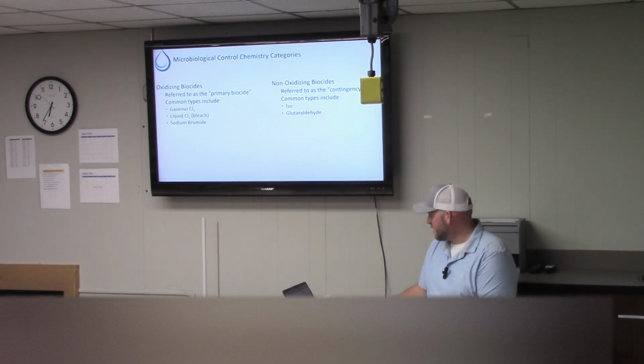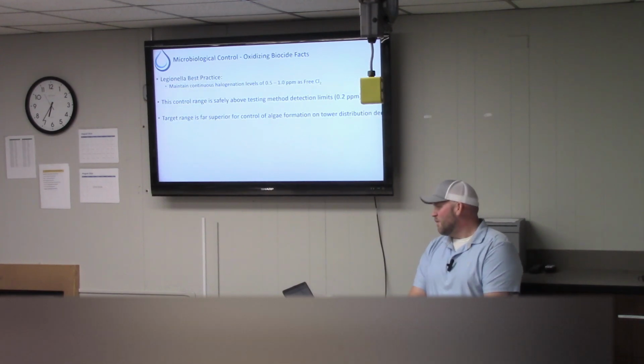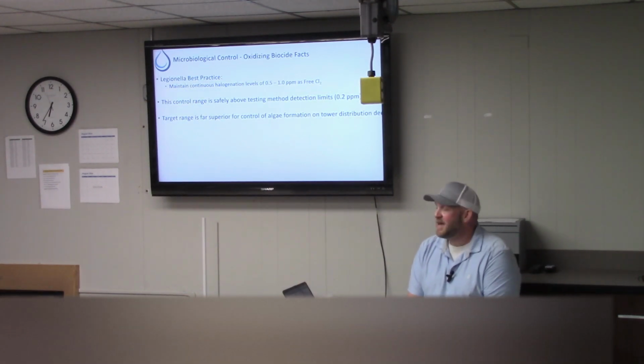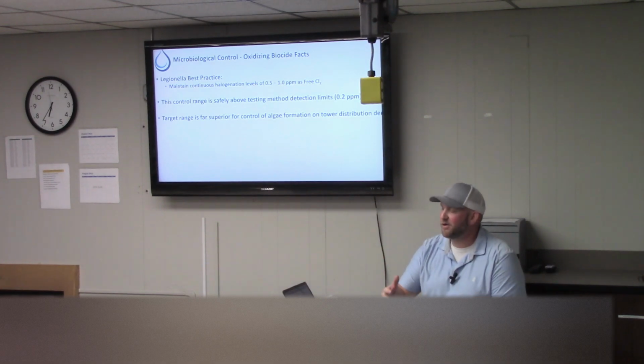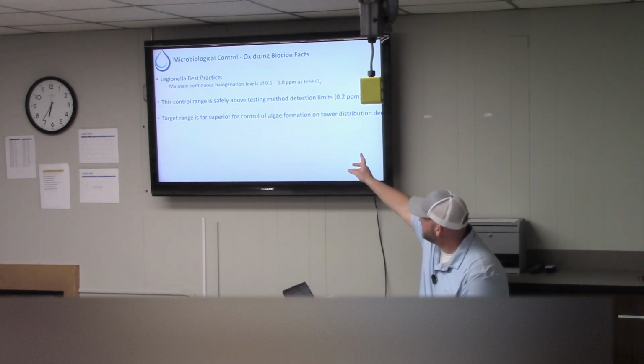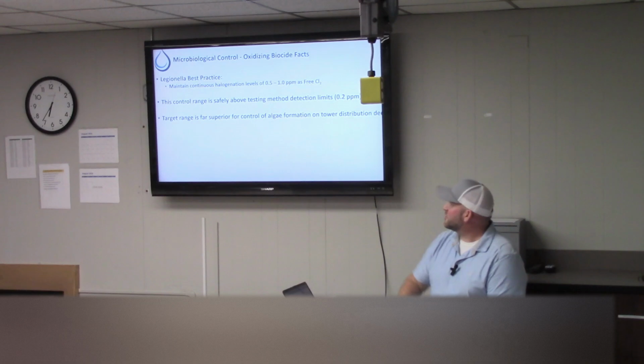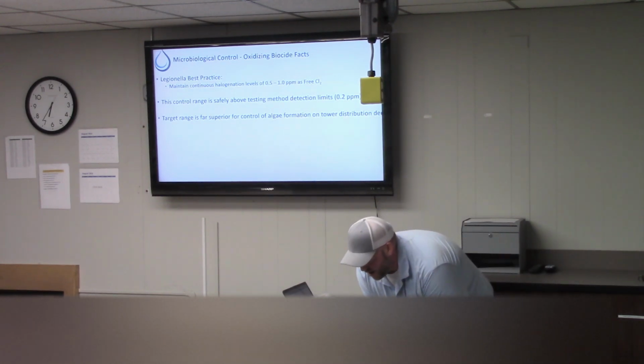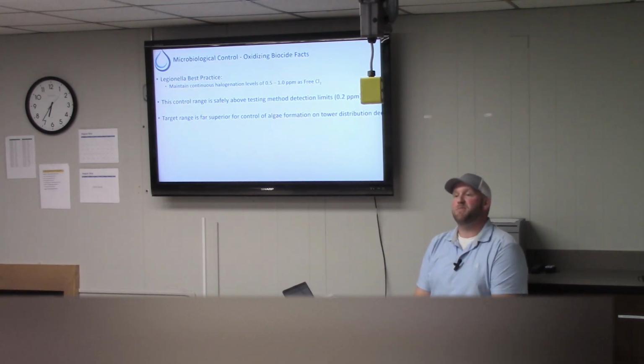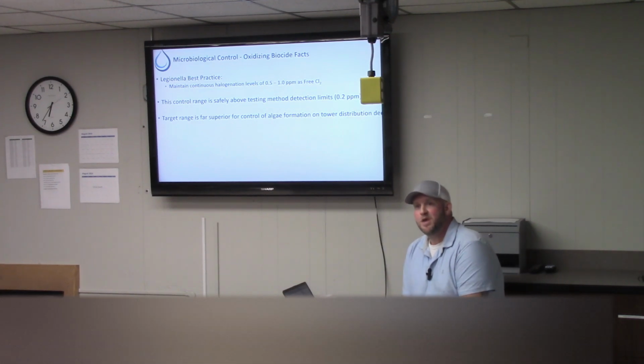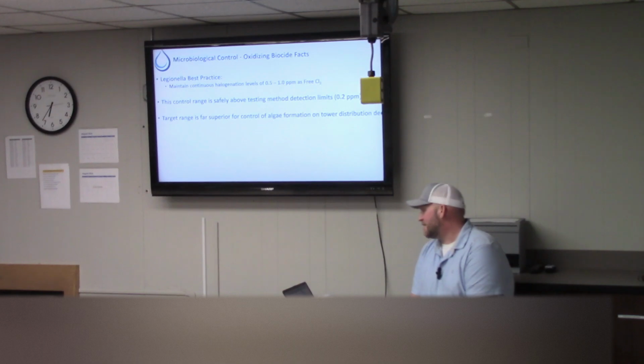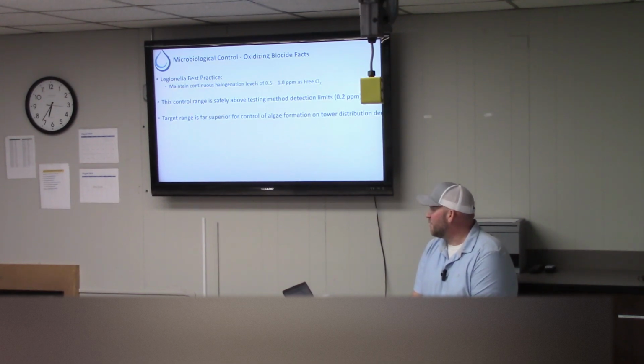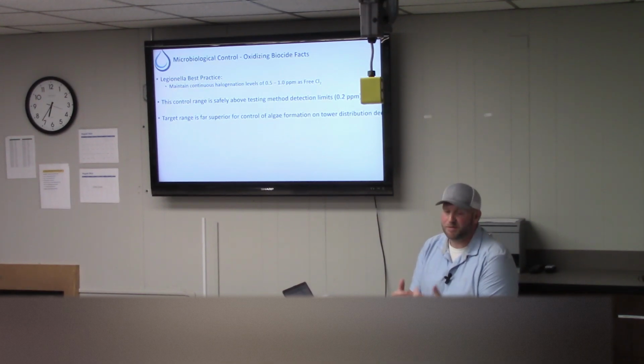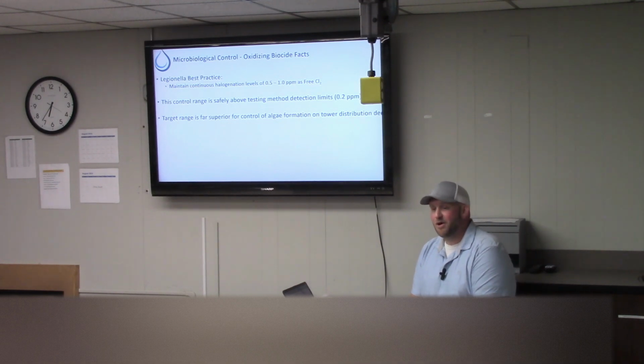When we look at the Legionella best practice, I know I spoiled it earlier: 0.5 to 1 ppm free CL2. This control range is safely above the detection limit for the meters you'd have access to, which gives you confidence that the number you're testing is real. The target range helps keep Legionella away, and it also matters for distribution decks on cooling towers.